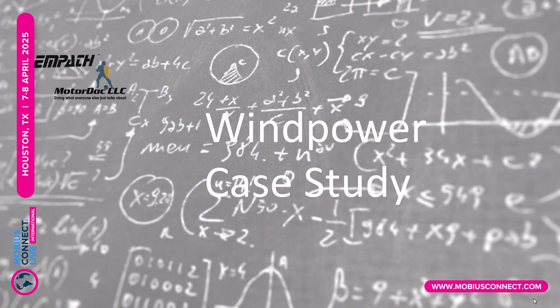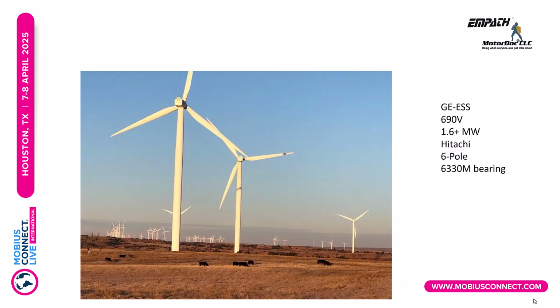So let's hit one more case study here if we got a chance. This is a GE wind turbine. What they had done is they had replaced a bearing, and they had set the coupling back up to the gearbox, and they did a before and after. And this is really good because it just so happened we had the exact same wind speeds and everything else. Everything was exact within a couple of watts, a couple of kilowatts.